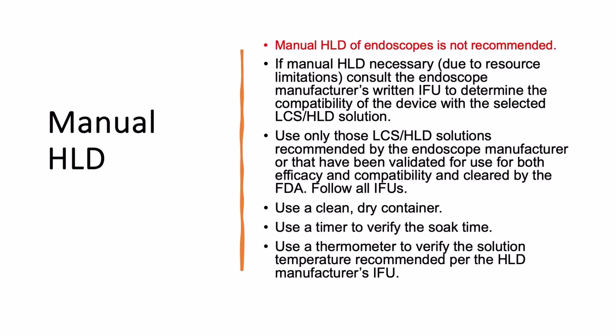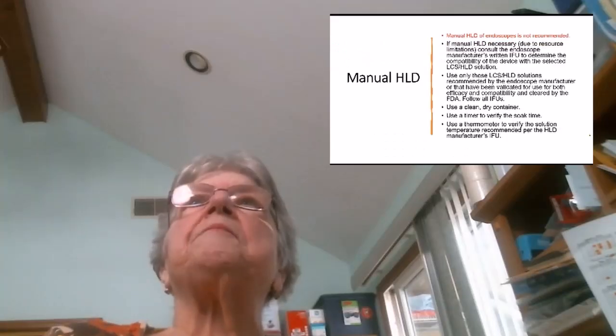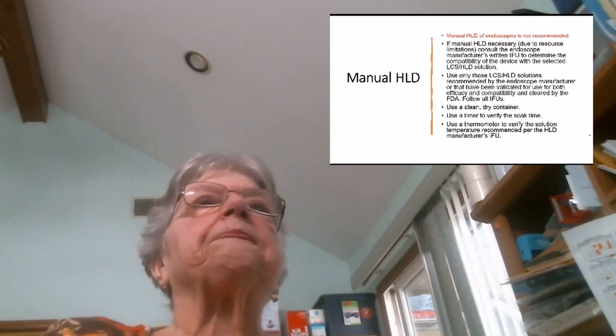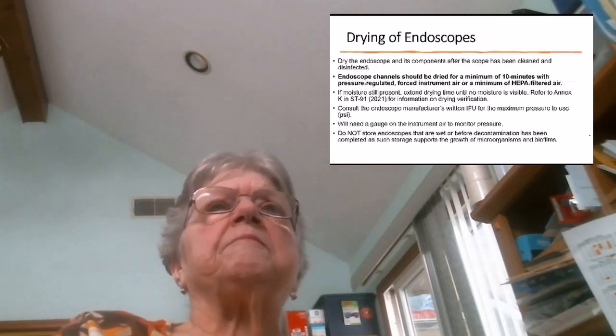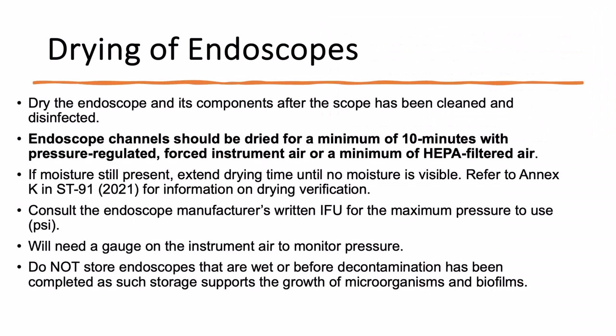You should use a clean, dry container, use a timer to verify the soak time, and use a thermometer to verify the solution temperature recommended according to the high-level disinfectant manufacturer's IFU. And you should document the soak time, and you should document the temperature. Drying of endoscopes is very, very important. Endoscope channels should be dried for a minimum of 10 minutes each with pressure-regulated forced instrument air or a minimum of HEPA-filtered air. If you still have moisture present, extend the drying time until you don't see any moisture, and there is an Annex K for more information on drying verification.